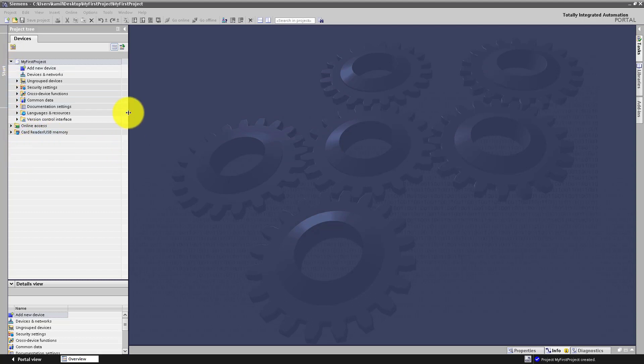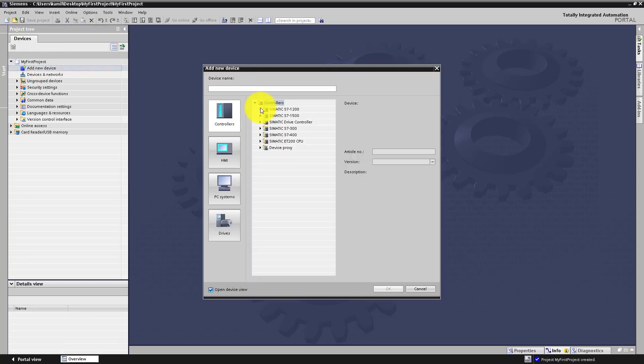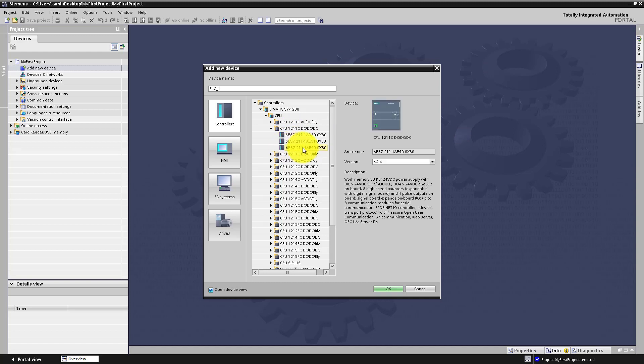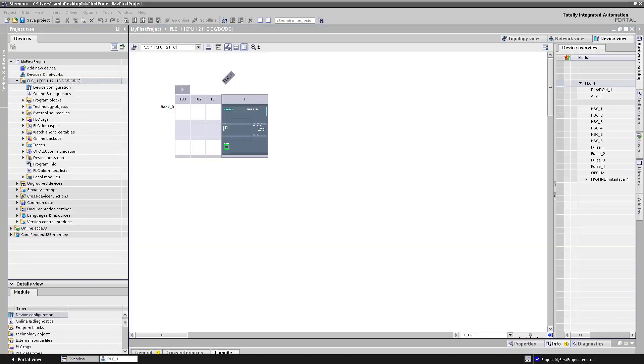On the left side you will see the project tree. Now click 'Add new device'. From the controllers choose SIMATIC S7-1200 CPU 1211C DC/DC/DC, and click on the last item on this list — this is the CPU with the newest firmware on the market. Choose firmware version 4.4 and click OK. A new device will appear in your project tree.